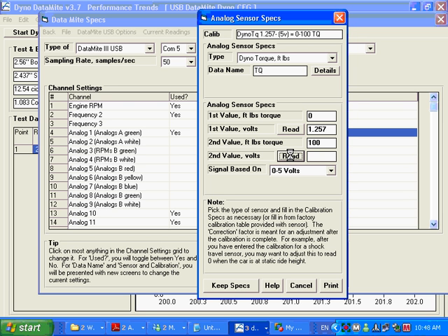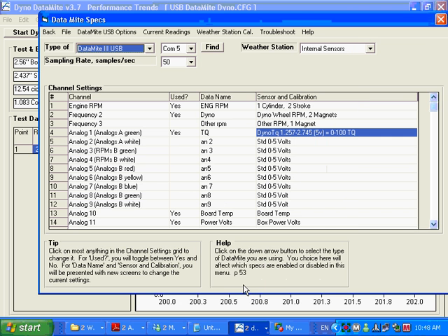So zero foot-pounds put out 1.257 volts, 100 foot-pounds puts out 2.745 volts. You can see these numbers are being stored up here in our calibration, and we're going to keep the specs. Now we've got a good torque calibration here.